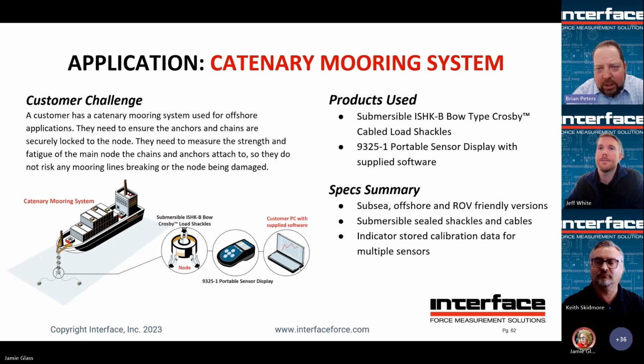All right, here's a mooring application. The customer wanted to be able to have submersible shackles. It was hooked up to a 9325 portable display instrument, which was very handy in that it could store calibration data for multiple shackles. So you hook up, transfer over to a different one. It would be able to load up the sensor and have that cal data already loaded in there, so they don't have to do any scaling. And the shackle is obviously submersible.